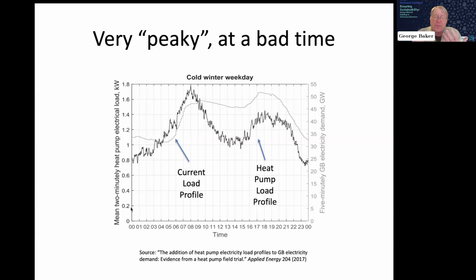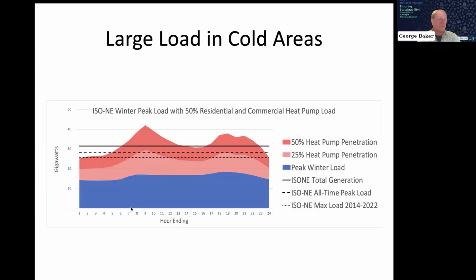Right, so on temperate days, on 40-degree days, you can generally get about 3 times as much heat out of the heat pump as the electric energy that you put in. That's called a COP of 3. On really cold days, that COP drops to between 1.5 and 2, especially for air-to-water heat pumps. And so on really cold days, the heat load goes up, but the electric load goes up by a whole lot more. Right? And so this is a picture from a study that was actually done in Great Britain almost 7 years ago now, but showing just how peaky the electric load is for a heat pump heated house. Okay, so what does this mean?